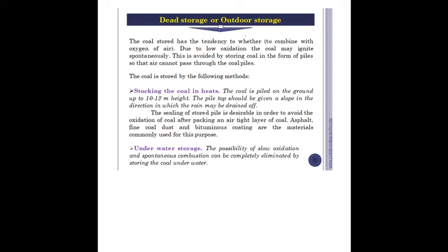Dead storage, or we can say outdoor storage. Coal has a tendency to weather, to combine with oxygen of air. Due to slow oxidation the coal may ignite spontaneously. This is avoided by storing coal in the form of piles so that the air cannot pass through the coal piles.